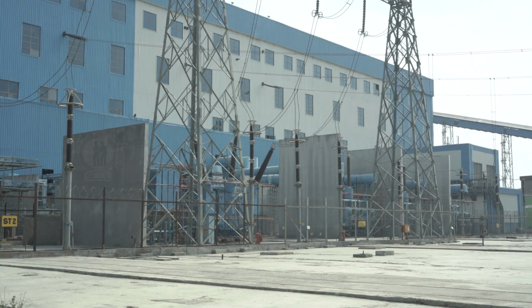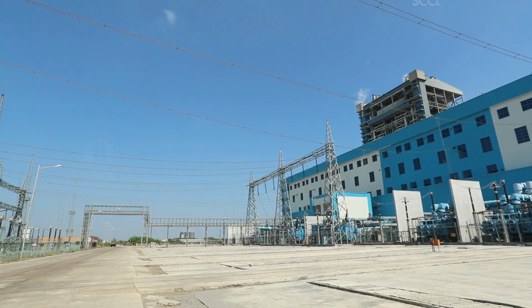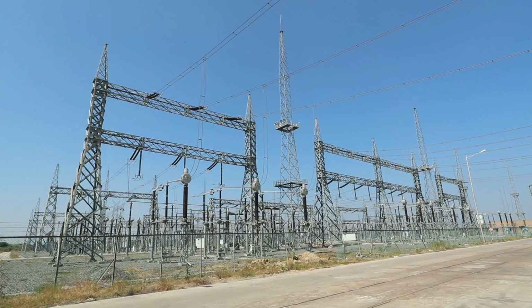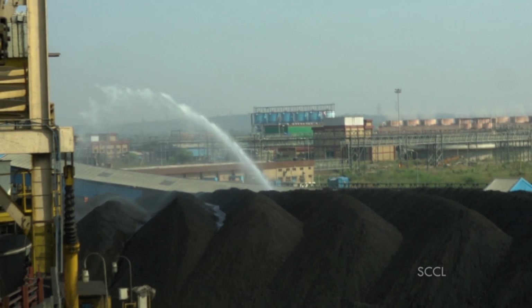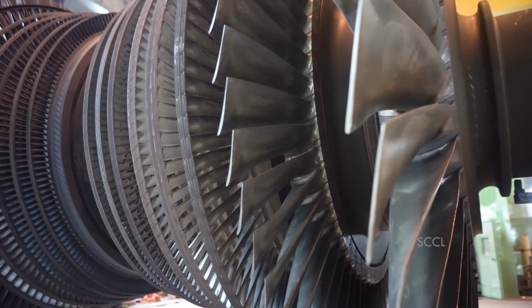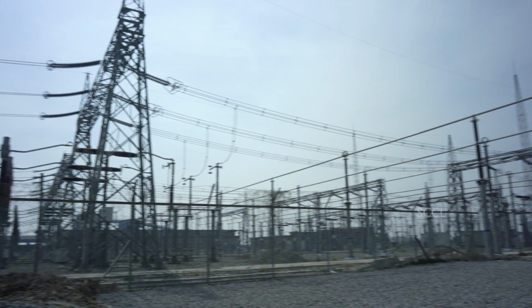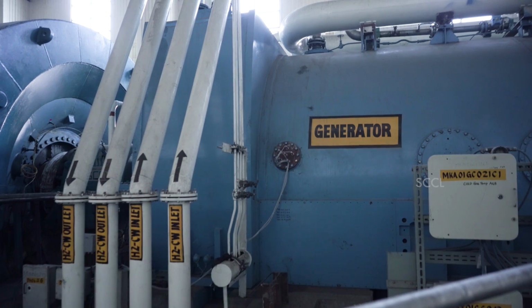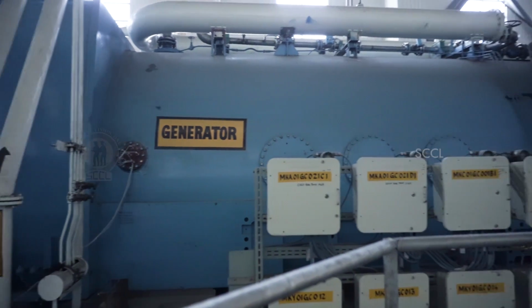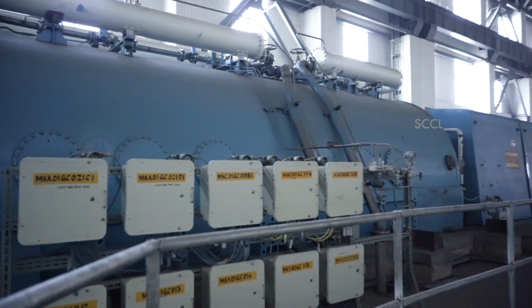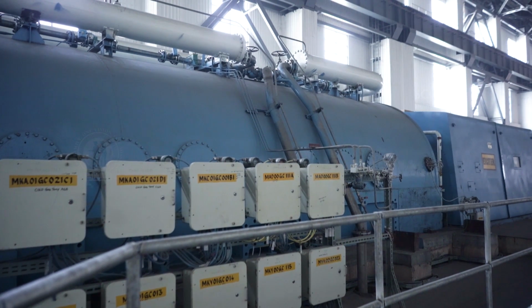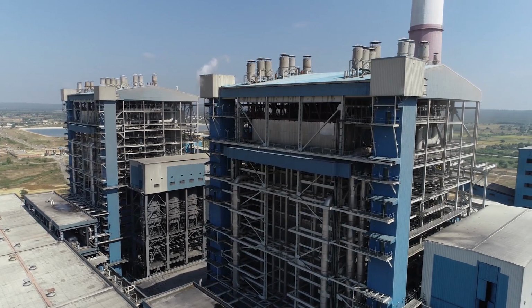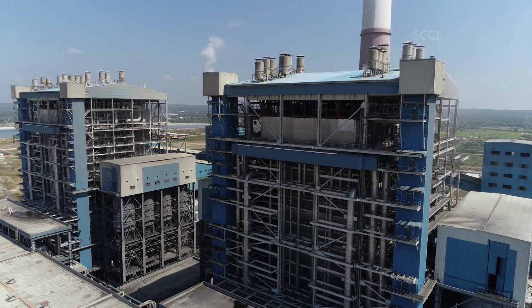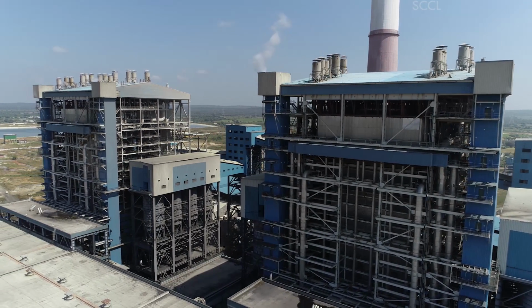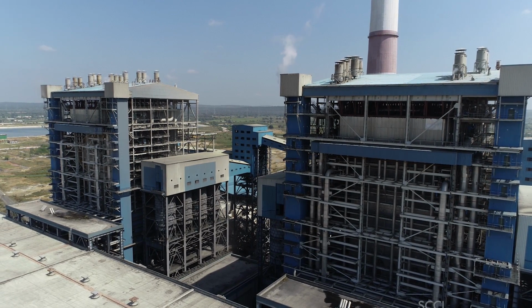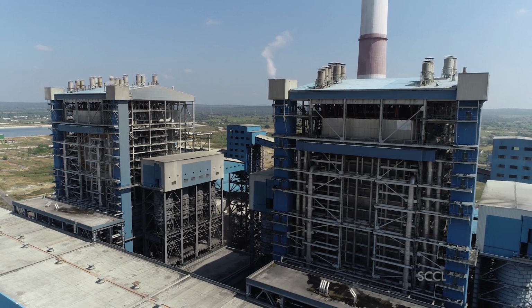Which is stepped up to 400 kV through transformers and is transmitted through 400 kV switchyard to the power grid. So, basically burning coal boils water to make steam and spin many tons of stainless steel to create thousands of volts of electricity. The generator continuously creates an electrical charge of 21 kV of electricity, which is equal to 600 megawatts, that is, 6 lakh units per hour. The total power generated by each unit is 144 lakh units and a total of 28.8 million units of power is generated by STPP every day.